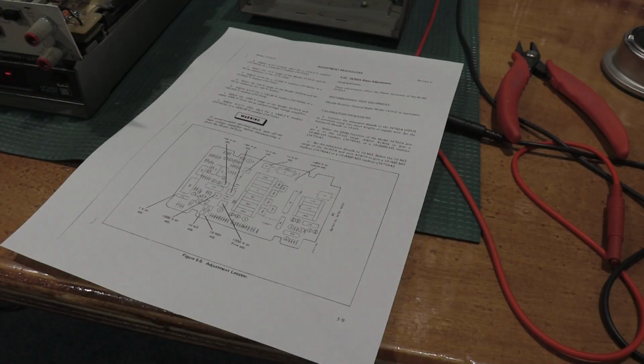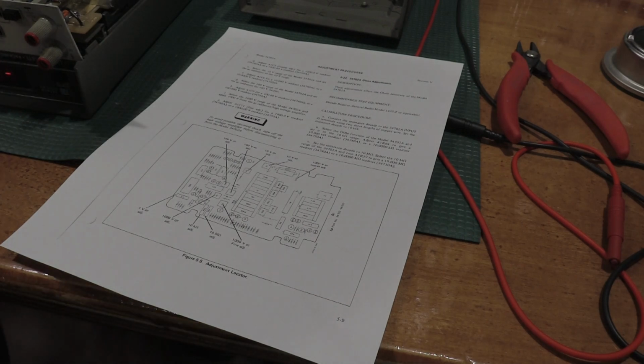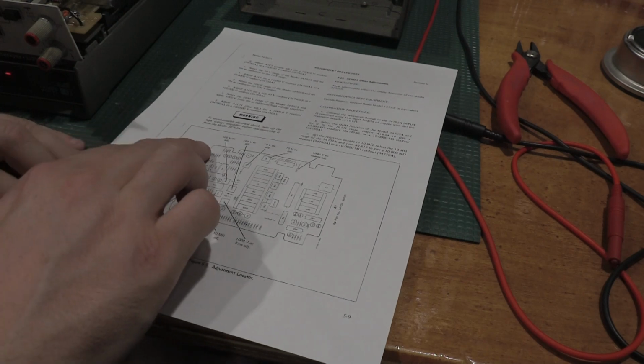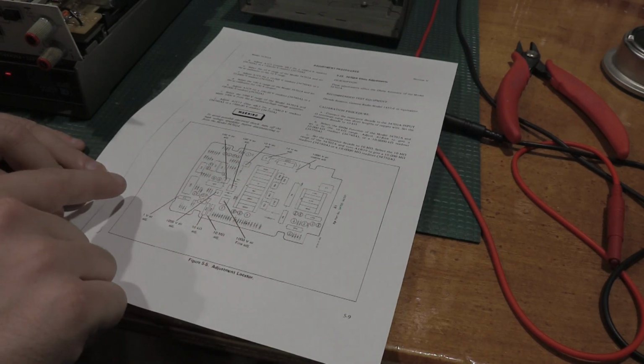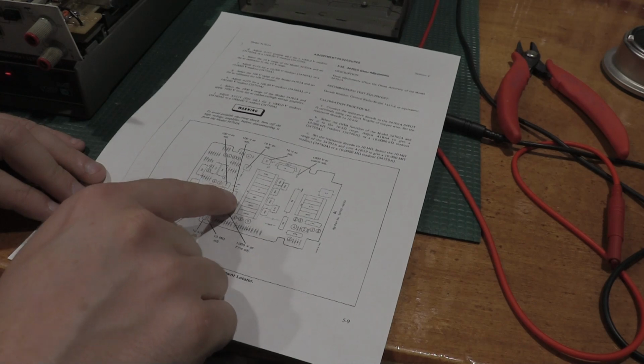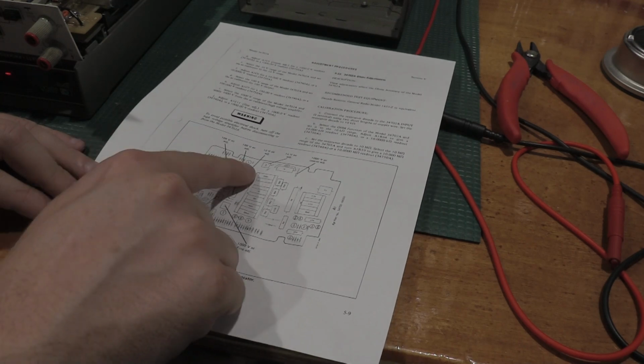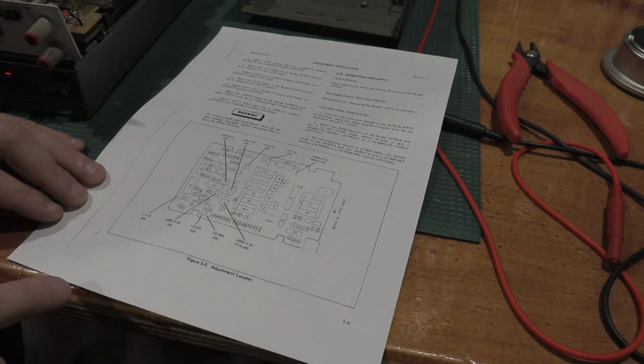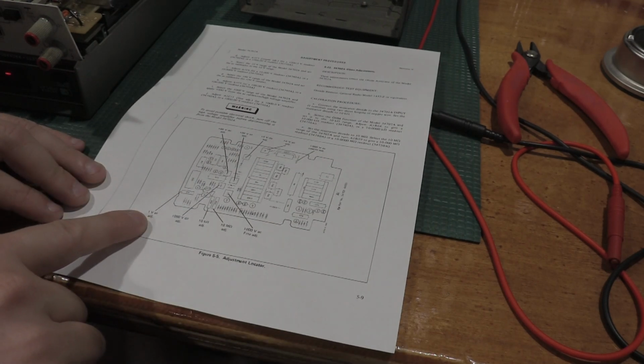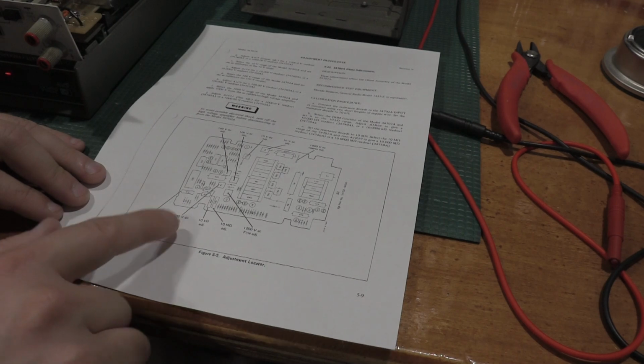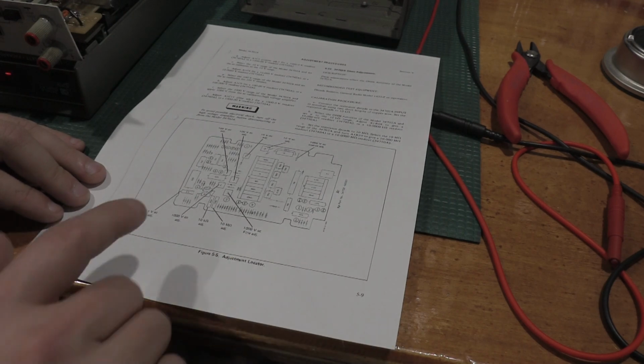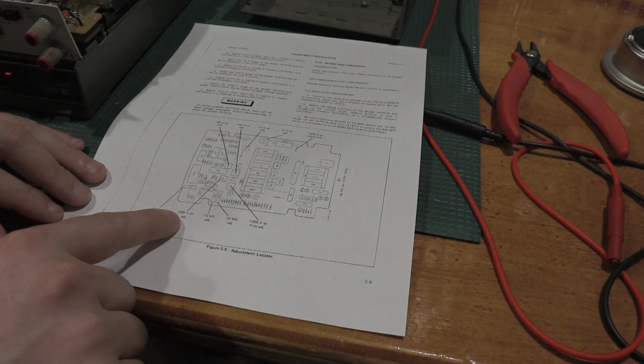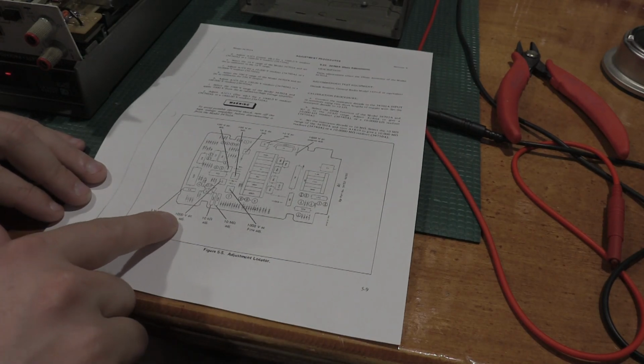Okay, the alignment process on this particular meter is relatively straightforward. Give it appropriate sources on the correct inputs and adjust all the points on the meter board. Voltage, so we have 100 volts DC, 100 volts AC, 10 volts DC, 10 volts AC, 1000 volts DC, 1 volt AC, and then we have the resistance ranges. 1000 volts DC coarse and 1000 volts DC fine. Yep. And the resistance ranges.